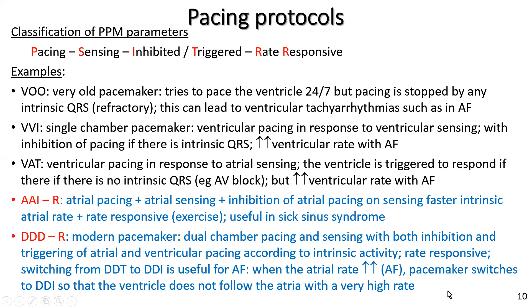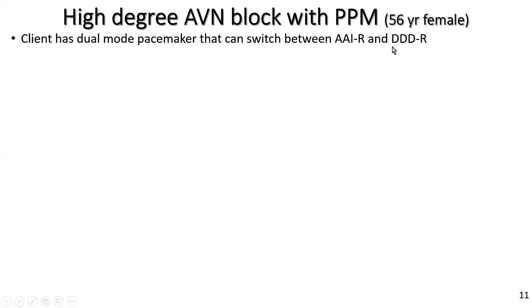So coming now to just a little bit on the client that I'm going to talk about in part 3 of this video series, just on the topic of AAI responsive and DDD responsive pacemaker. This client actually has a dual mode pacemaker that can switch between the atrial dependent pacemaker mode and the dual mode here. So in the atrial dependent mode, where there is atrial chamber pacing and sensing, here the pacing spike was put in. Incidentally, you wouldn't see that. The pacing spike's been put in here because it didn't get a P wave, so this would be, say, on standstill. It's put in a pacing spike for the P wave, and then the ventricle is followed. So there's no ventricular pacing here at all. The ventricle is followed because the AV node is intact, and you've got normal conduction after the pacing spike.